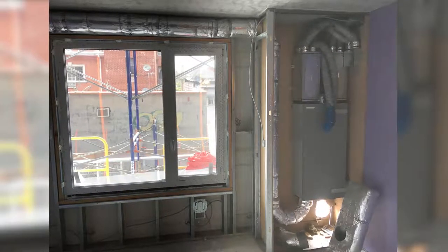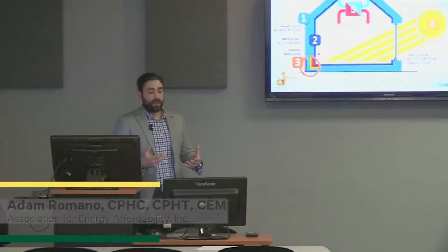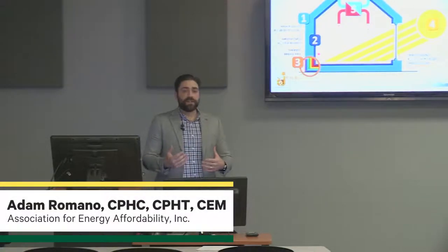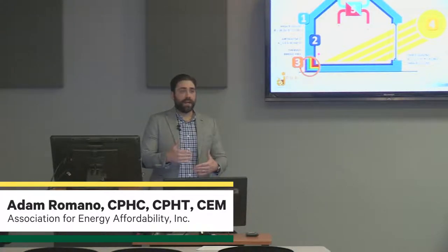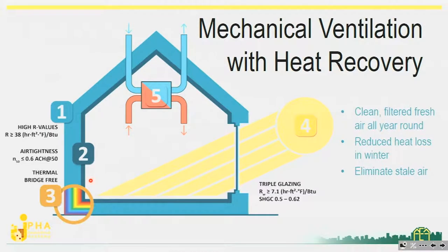The next design criteria is to make sure that we're using the appropriate mechanical ventilation system. We want to make sure it's incorporating some sort of heat recovery, whether it's a heat recovery ventilation system or an enthalpy recovery ventilation system. We want to make sure that any exhaust air leaving the building has its thermal energy recaptured and brought back in, so we don't have a negative consequence against our performance by bringing in unconditioned air from the outside.